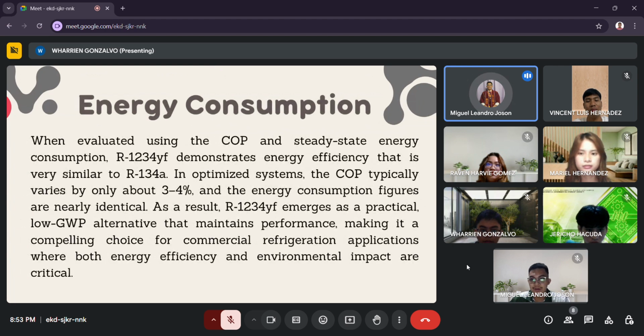Then, the energy consumption. When evaluated using the COP and steady-state energy consumption, R-1234yf demonstrates energy efficiency that is very similar to R-134a. In optimized systems, the COP typically varies by only about 3 to 4%, and the energy consumption figures are nearly identical. As a result, R-1234yf emerges as a practical, low-GWP alternative that maintains performance, making it a compelling choice for commercial refrigeration applications where both energy efficiency and environmental impact are critical.